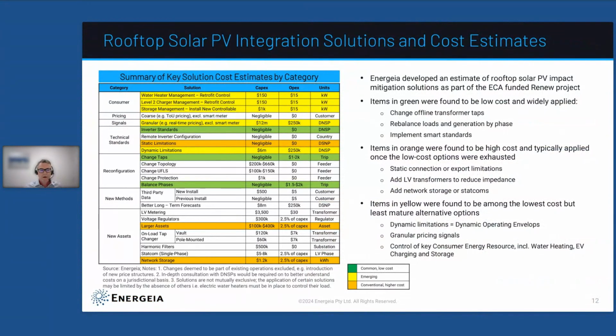And what we're showing here is when you're trying to mitigate those costs from solar PV integration, the items in green, inverter standards, changing the taps of offload tap changers on transformers, and rebalancing the phases have been the go-to solutions for distribution networks and are relatively low cost. With the possible exception of inverter standards, in that it can increase the level of curtailment that you see on these systems. When these green items start to no longer be effective, the networks have to look at things like putting in static limitations, so reducing capacity from 5 kilowatts per phase to less, installing larger assets or more assets, in particular more transformers on the low voltage system, or even looking at StatComs and storage.